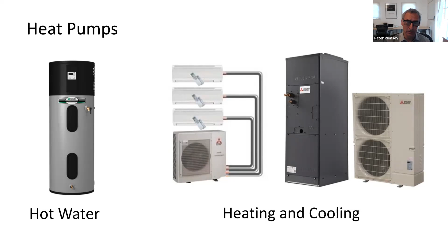One thing we're seeing in commercial buildings is the use of variable refrigerant flow, VRF systems, and we're seeing that take hold very quickly in a large part of the country. I think it's probably the most significant development in HVAC in the last 5 years. At a larger scale, it uses the refrigeration cycle to provide either heating or cooling to the building. You're using the same compressors, leveraging the technology you already need to install in the building for cooling, and it can now do heating.